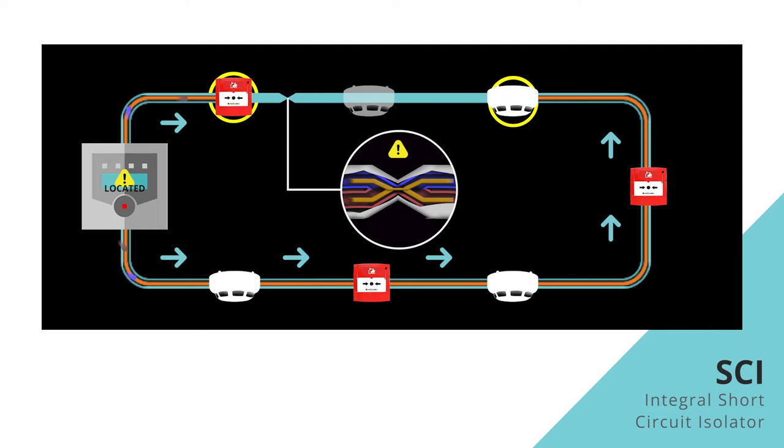This means that on either side of the short circuit the voltage can continue to flow, and the panel can still supply power and receive data from the loop devices. This happens instantaneously, and not only does this maintain the loop's integrity, but the section of loop that's been compromised is isolated, hence the name.